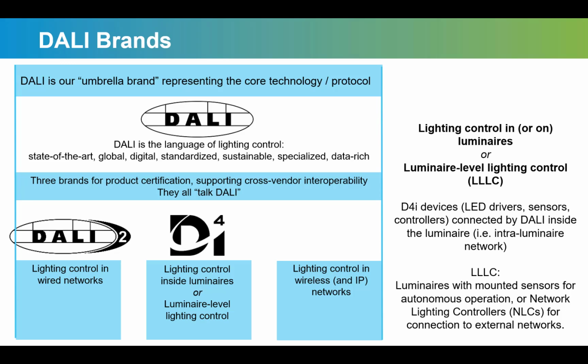So if you've got luminaires all in a row, you're going to have drivers in intermittent spaces, but they're not going to be one for one. That's very different from having one for one with integrated sensors in each fixture. When it comes to integrating with HVAC, it's the D4I opportunity with integrated sensors that gives you a chance to have these overlapping zones.